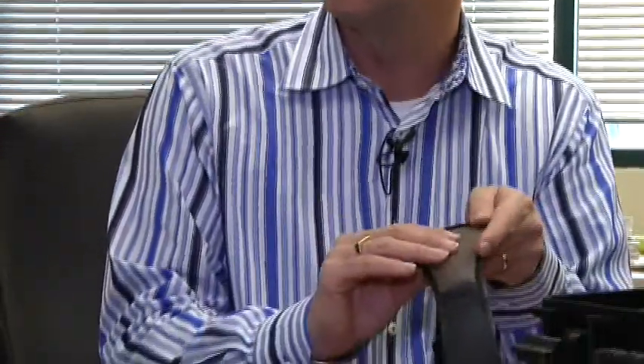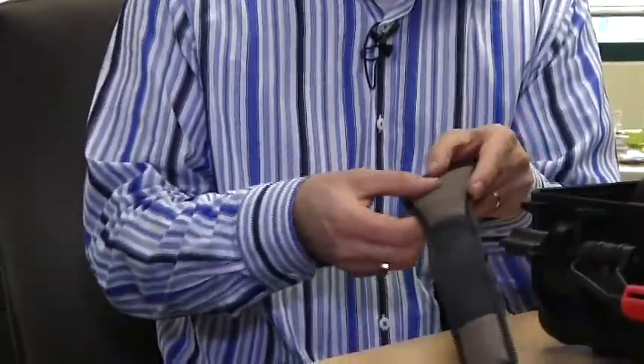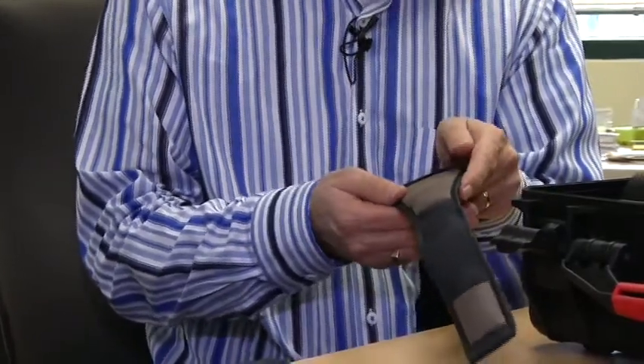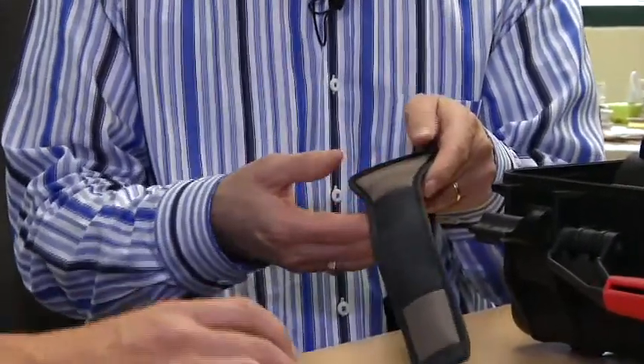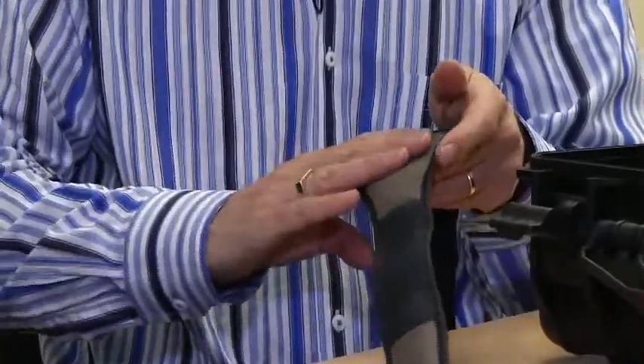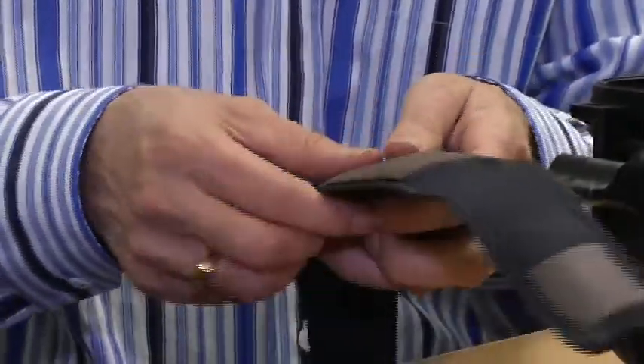So this is special fabric that you guys make, or somebody makes for you? So we have other partners that make the actual fabric. So this has fabric circuitry under here. So different layers of fabric, which essentially this acts like a capacitor, a variable capacitor. So as you apply pressure, the capacitance changes, and so we detect that. We're transmitting a signal into that and detecting the output of that to generate a breathing waveform.